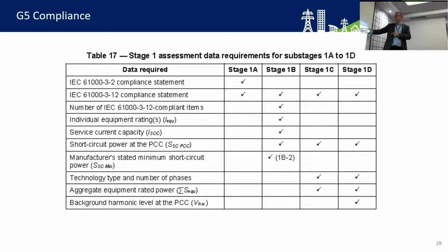61000-3-2, albeit it'll have to be sort of 32 amps or below, that's a notification, connect and notify us. If it's above 32 amps but below 75 amps, is it compliant with 61000-3-12? That's also a bit of a subsection on stage 1B, I think it's got 1B1 and 1B2, but is it compliant with this standard and subject to a minimum fault level? So that's the information you'd have to provide.